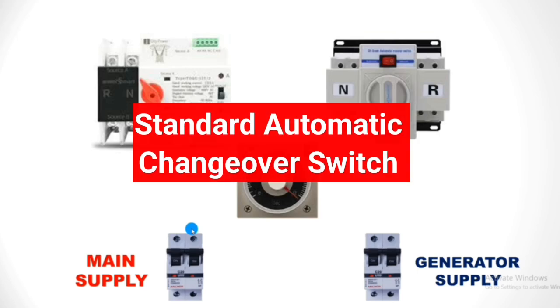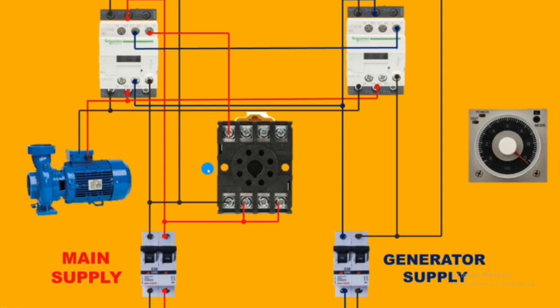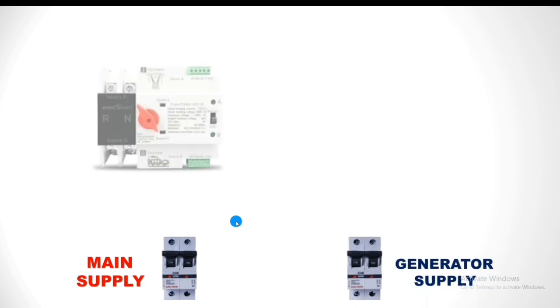In this video we are going to learn about a standard automatic changeover switch wiring and working. First, let's understand why we are calling it a standard automatic changeover switch. For example, if we have two power supplies — the first is the main power supply and the second is generator power supply, which could also be an inverter or solar power supply.